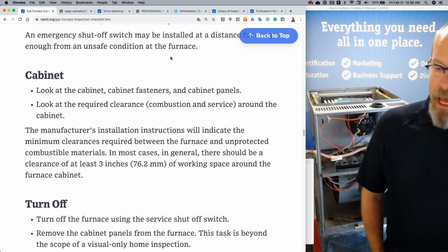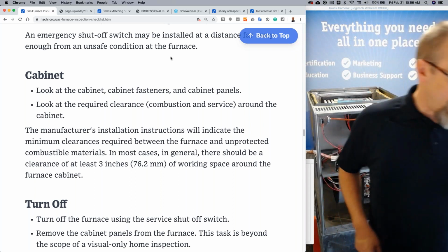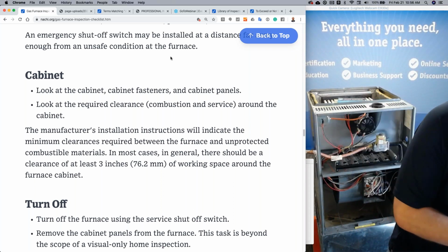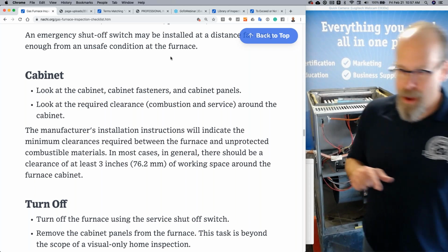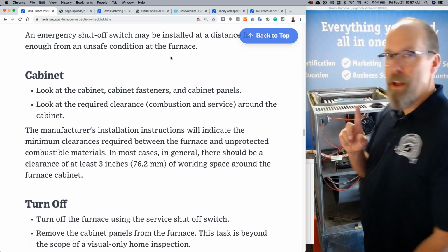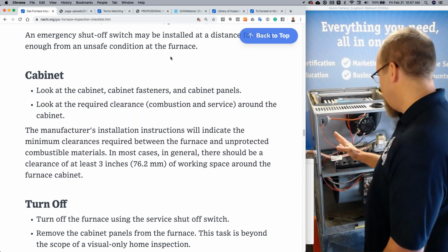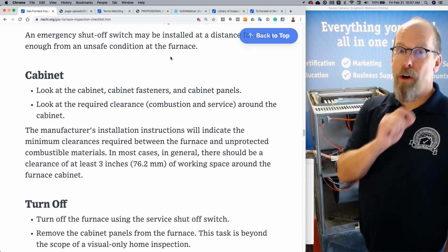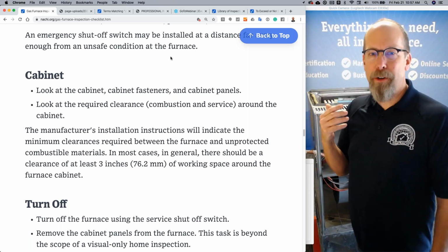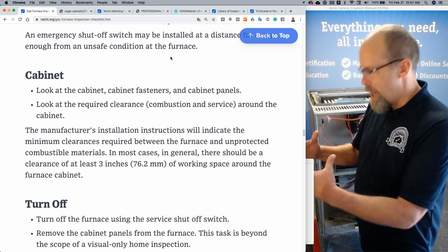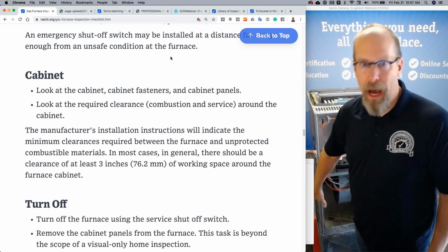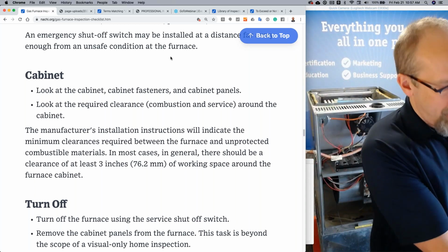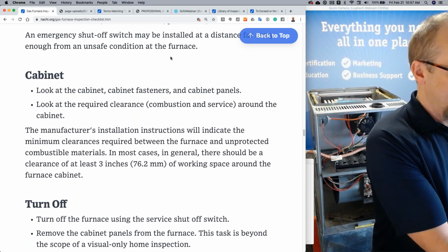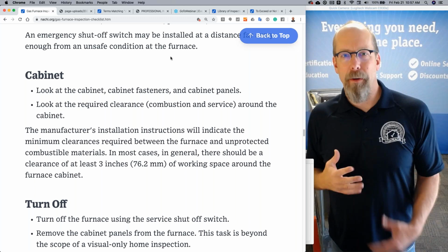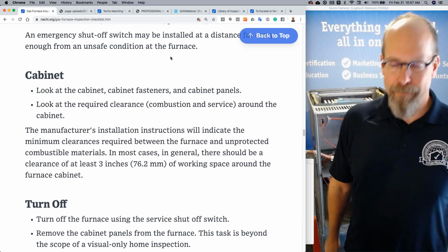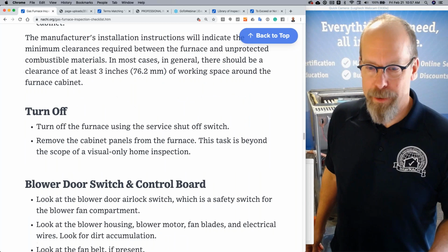In most cases, in general, there should be a clearance of at least 3 inches of working space around the cabinet. However, a lot of the local code, or the manufacturer's label, will actually say 0. But for me, as a home inspector, it's kind of strange to snug a furnace cabinet right up against the wall, even if there's drywall and protection, right? A good 3-inch clearance is probably a best practice. But again, we're not code inspectors, thank goodness.